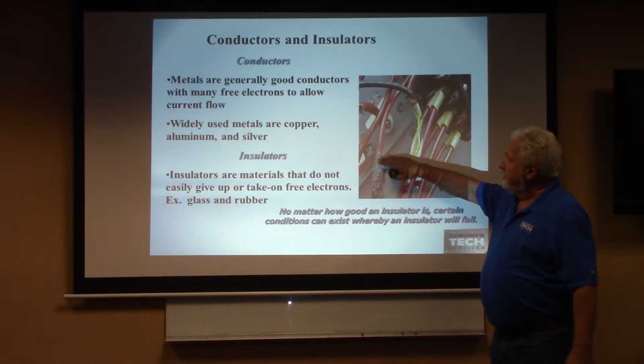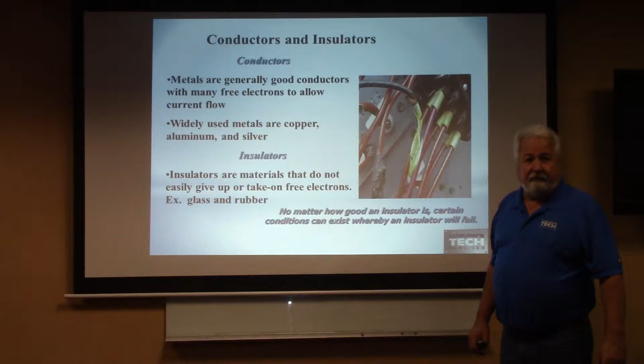No matter how good the insulator is, there are conditions where I can make that insulator fail. In this particular case, we had a couple of wires leaning up against each other. They started heating up, and current started going from one conductor through the insulator to the other conductor. Somebody decided a wire nut would probably be the best way to fix that, and obviously that didn't work out very well either.